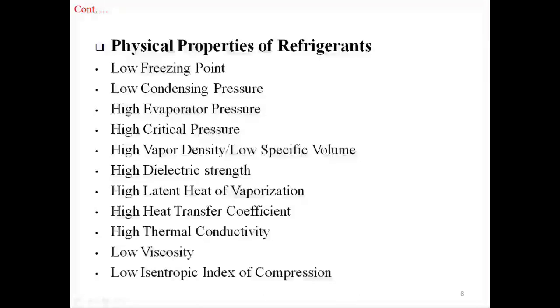Dielectric strength should be high to avoid short circuits. Refrigerant should have a high value of latent heat of vaporization so that it can extract more heat per kg of refrigerant, which increases the COP of the system. Refrigerant should have a high value of heat transfer coefficient, resulting in smaller area and lower pressure drop, making equipment compact and reducing operating cost. Refrigerant should have a low value of viscosity, as it leads to high heat transfer coefficient and smaller frictional pressure drop. Refrigerant should have a low value of isentropic index of compression so that the temperature rise during compression will be small.